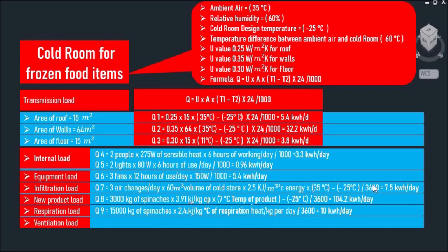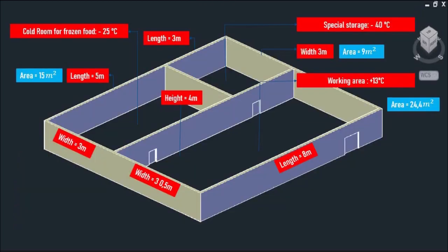And adding these all numbers in and multiplying by a safety factor of 1.1, that will give you your total cooling load for the first cold room. For the second cold room and the working area, I will talk about them in my next video.